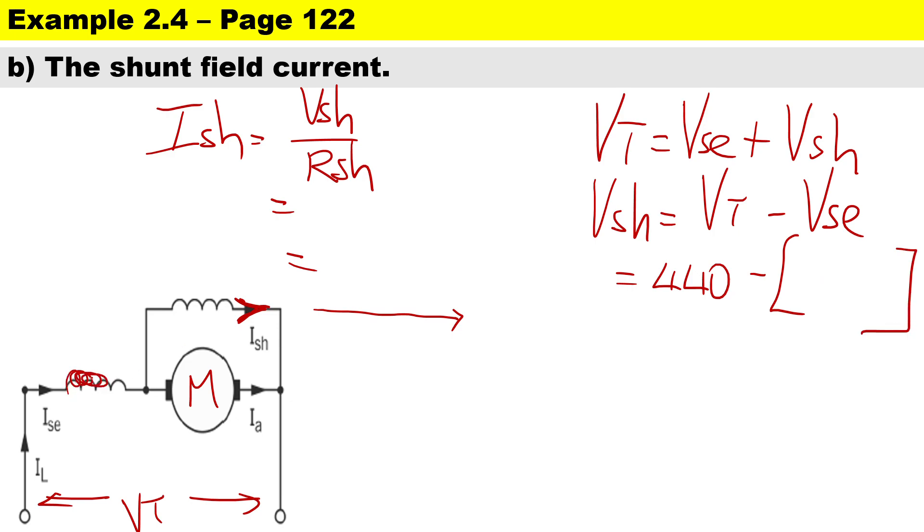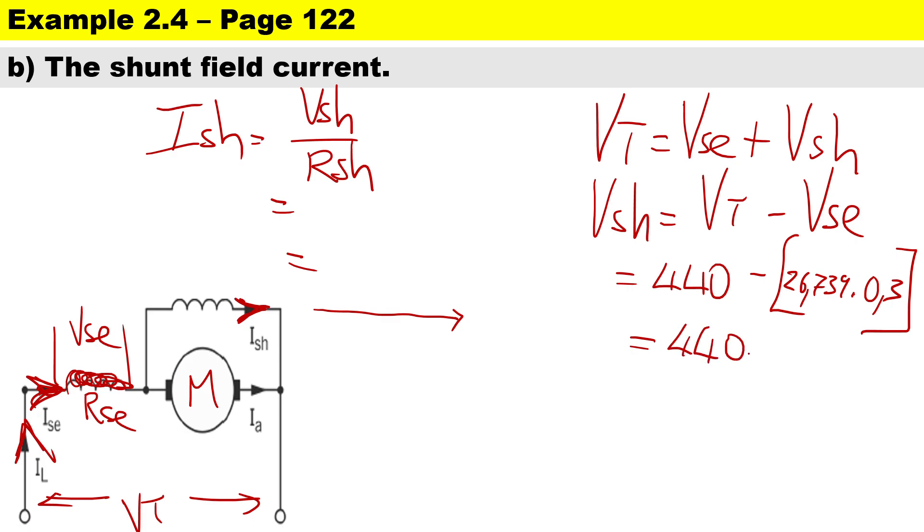To calculate Vse — the volt drop across the series winding — it is the supply current IL multiplied by Rse. The supply current is the same as the series current, the same current that passes through the series winding, which was 26.739 amps, and Rse is 0.3 ohms. So Vse = 26.739 × 0.3 = 8.022 volts, and therefore Vshunt = 440 minus 8.022 = 431.978 volts.